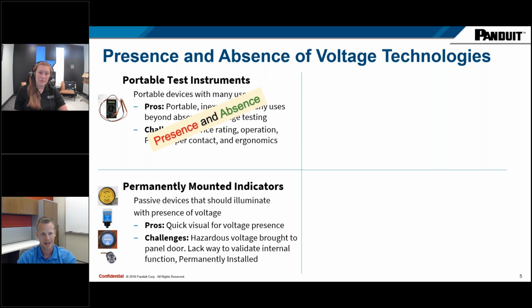That's the pro. The hazards or challenges with them are that hazardous voltage is typically brought to the back side of that device, which is on the panel door typically. And they lack a way to validate that the function of the device is working, right? You can't do a dead-live test on them. And then they are permanently installed. So if you want to know 3 spots within an enclosure, you need to install 3 of these devices. So it can add up price-wise, depending on how much information you're looking to get.